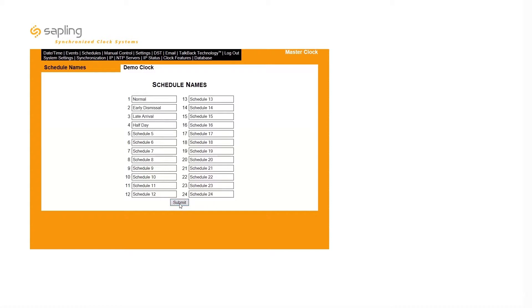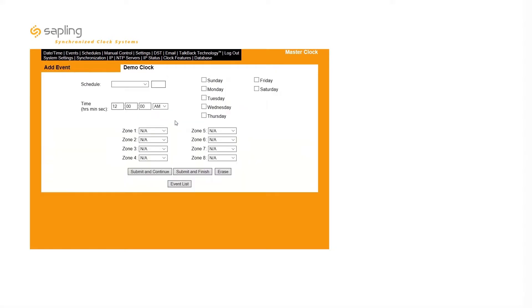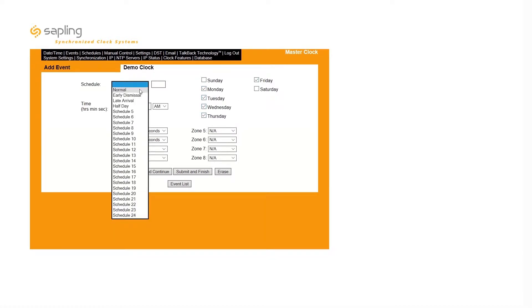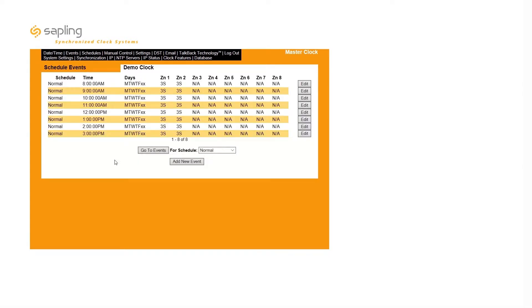To set up an event, click on the Events tab and select the Add New Event button. On the Event Configuration menu, a user can set the activation status of the relay, the time that activation will occur, which days of the week that activation will occur, and the schedule that the event should be assigned to. Click Submit and Finish to save your event.